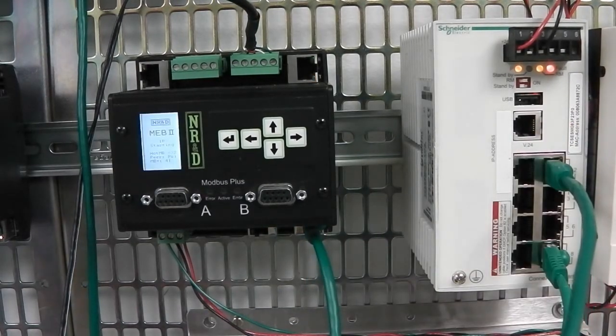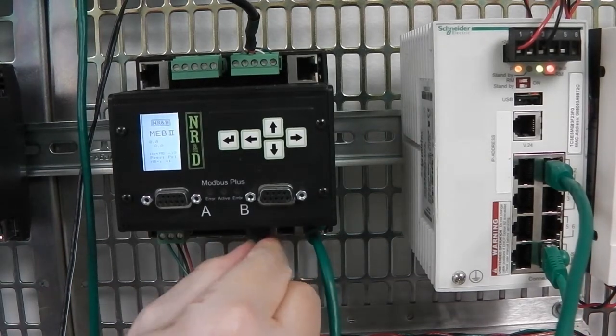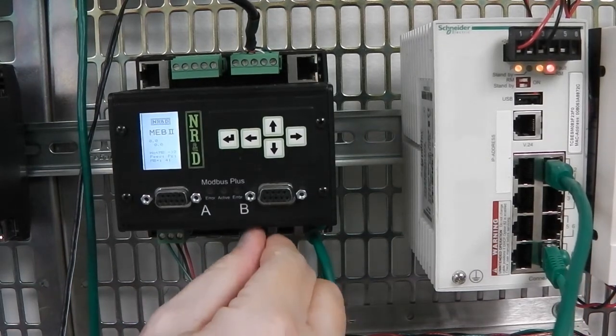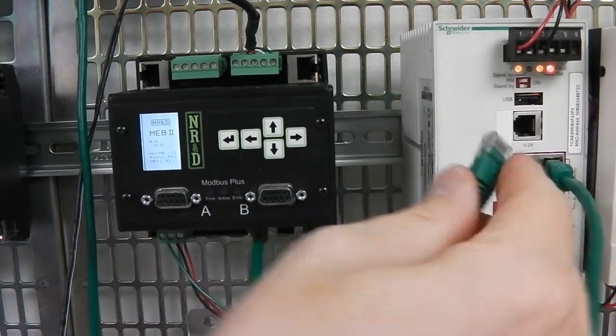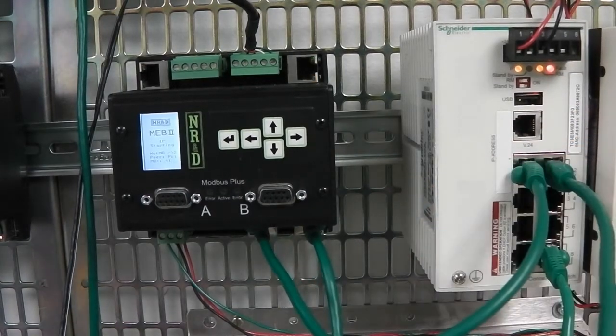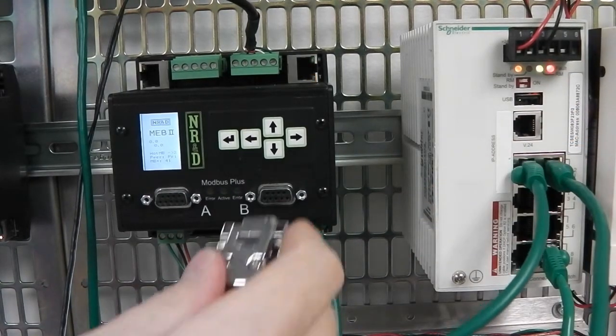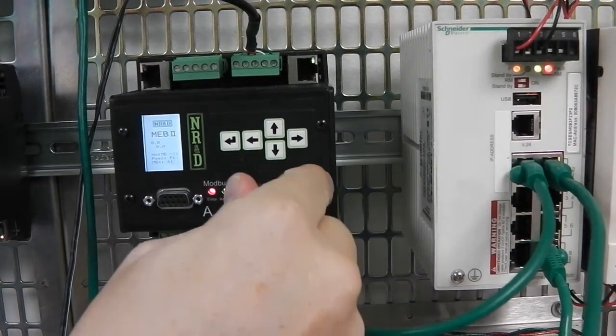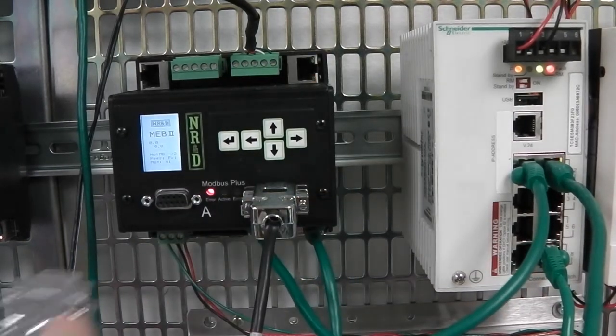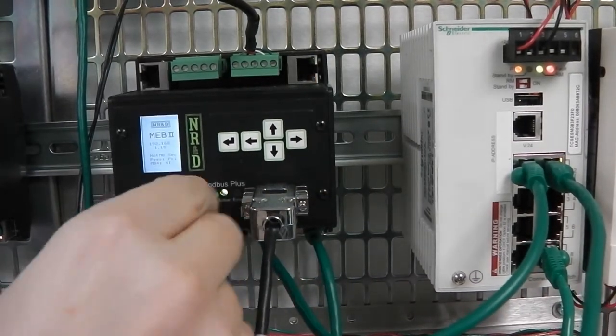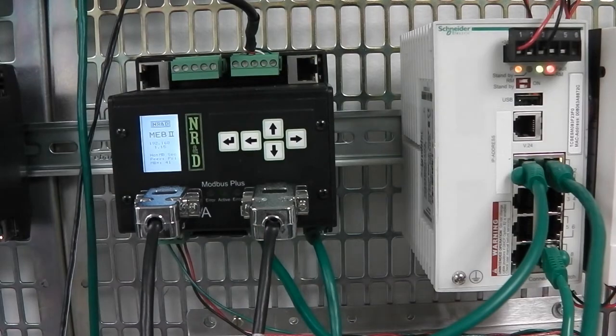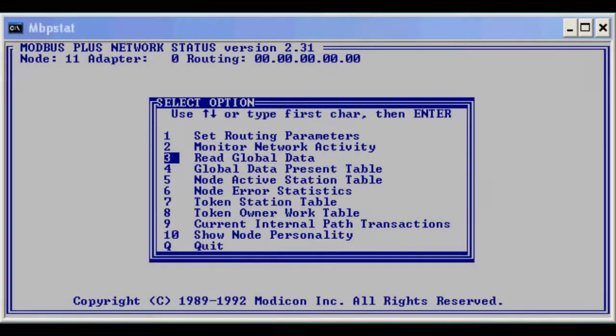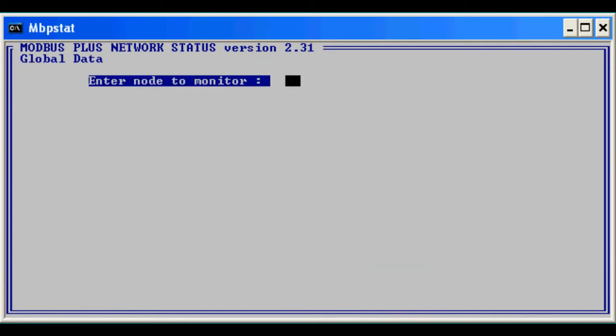Modbus Plus global data is used between the pair of MEBs. This data may also be viewed by any of the PLCs on the local Modbus Plus network. The MBP STAT program may be used to take a look at the global data. First, we look at the primary MEB at node 40.